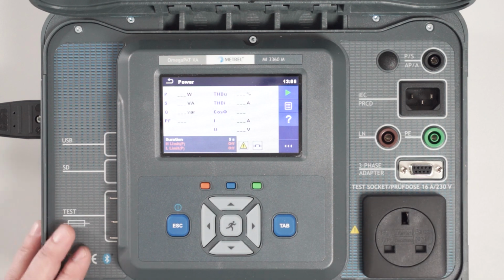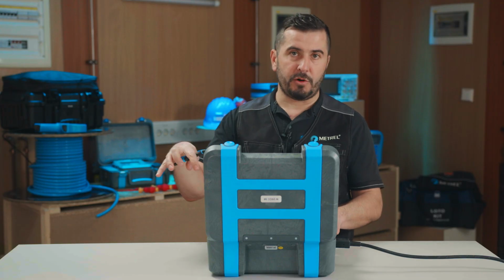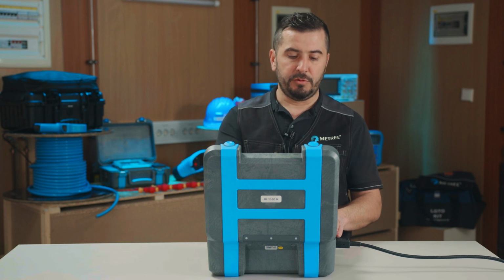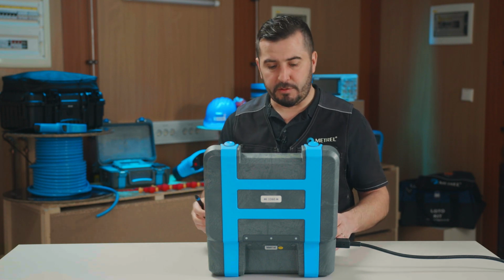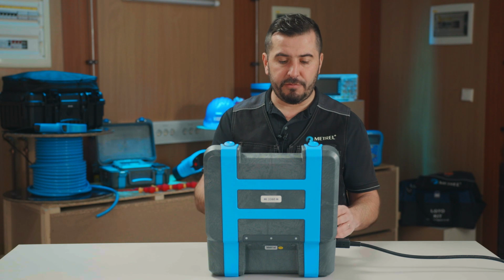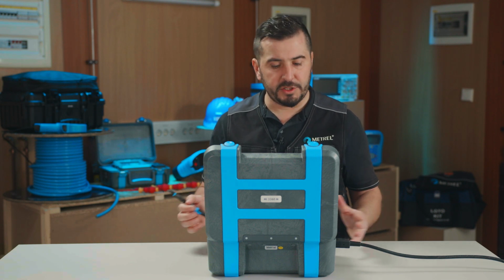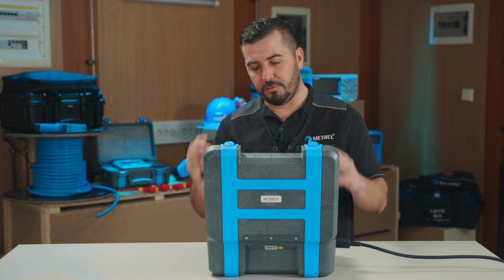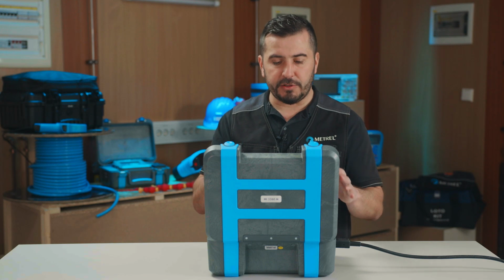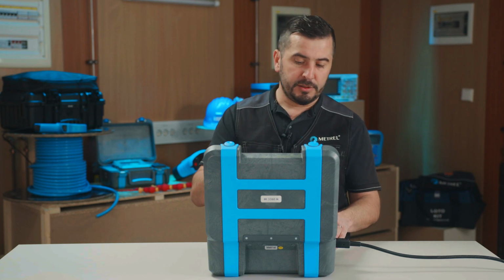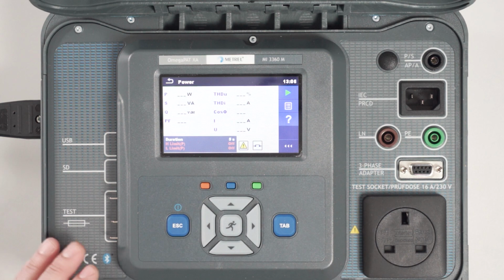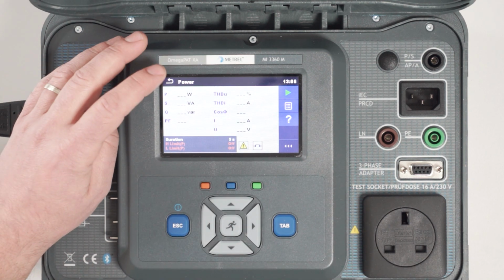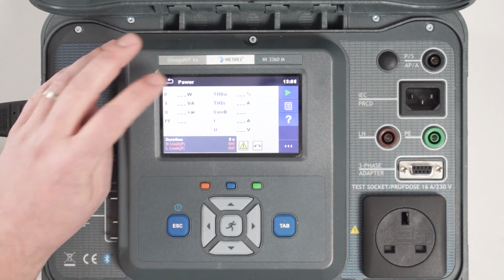Under the power, we have this function where we basically measure the complete power of appliance under test. So we have the real power, apparent power, we have power factor, we have total harmonic distortion on current, on voltage. So a lot of parameters inside this power measurement. This is very good for troubleshooting on your appliances.